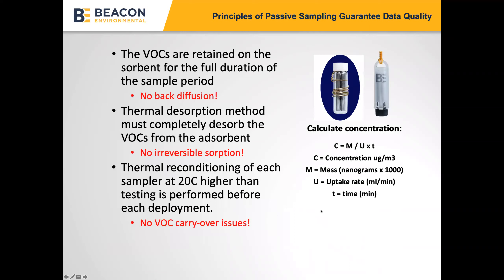For passive samplers to work, VOCs must be retained on the sorbent for the full duration of the sampling period with zero back-diffusion. The thermal desorption method Beacon uses completely desorbs VOCs from the adsorbent with no irreversible adsorption. Each sampler is thermally reconditioned at 20 degrees Celsius higher than the desorption temperature before each deployment, ensuring no VOC carryover issues — which is a common concern with canisters. Concentration is calculated as the mass collected on the adsorbent divided by the uptake rate and sampling time period.